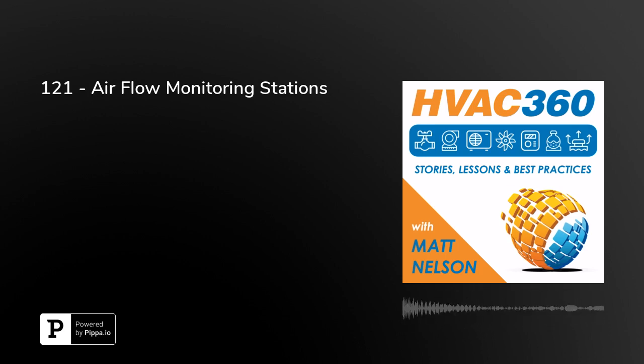Other things, fan inlets. You can have them on fan inlets, and they look a little bit different. They're smaller tubes, but again, depending on what the diameter of the inlet is, you can do a calculation, and you can do not only just one or double width, double inlet fan. You can do fan arrays with these things, so you can have multiple fans on the same monitoring station and do it that way. So again, whether you're in a ductwork, whether you're in an intake hood, whether you just want to slide a frame or need an integral damper, that's another form factor.